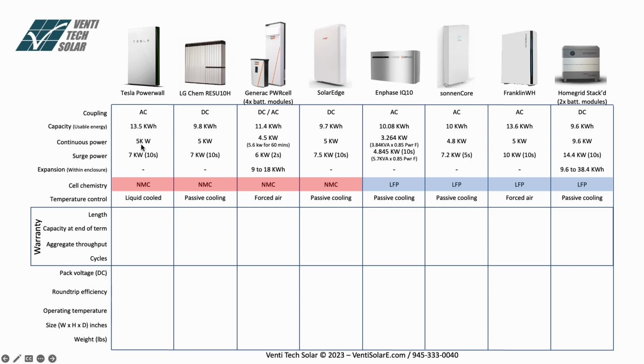Continuous power is typically half of the capacity, so 5 kilowatt for the Tesla Powerwall, 5 for the LG Chem, 4.5 for the Generac, 5 for the SolarEdge, 3.264 for the Enphase, and that's calculated based on the power rating and the power factor they provide. They don't provide a kilowatt continuous power number. They provide a number plus power factor. On the SonnenCore is 4.8, Franklin is 5 kilowatt, and the Home Grid is 9.6 with 2 battery modules.